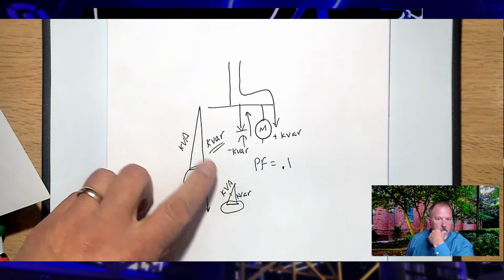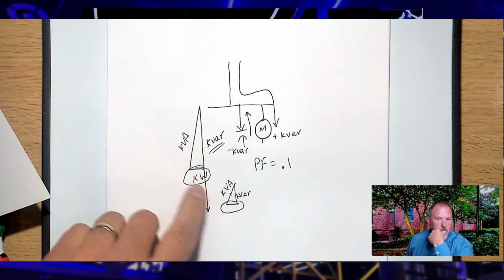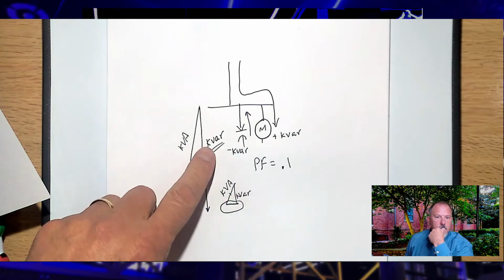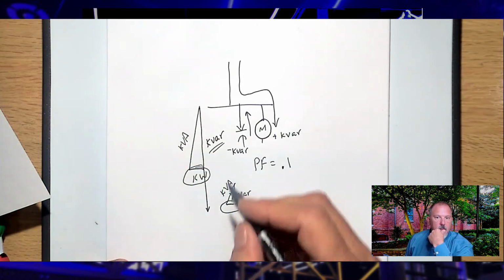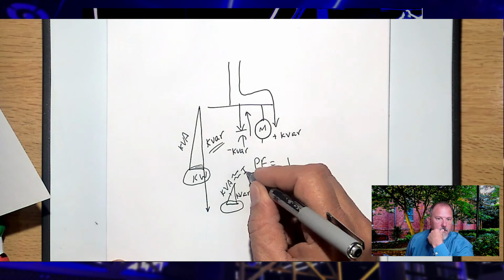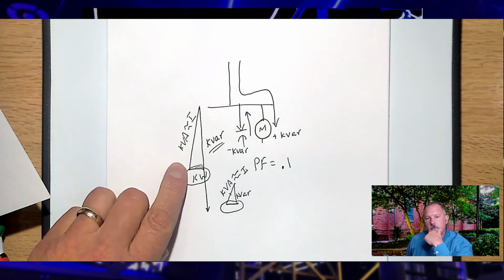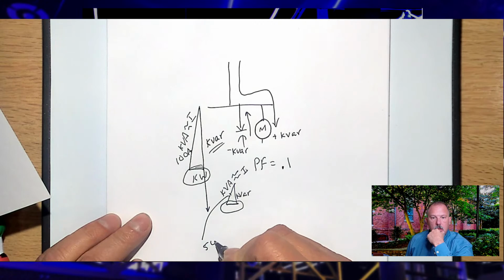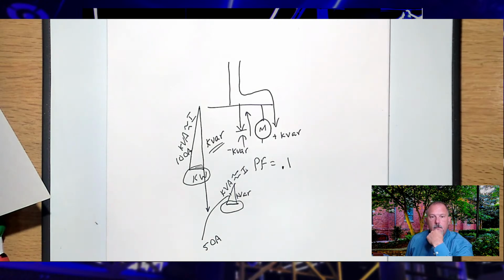So what has really changed here to here? Not my watts, but my kVA and my kVAR. So if I show you amps, amps are proportional to kVA. So if I told you I had 100 amps here and 50 amps here, I could be totally truthful to you. But if I didn't know better, I might tell you that I'm saving 50% of my power.